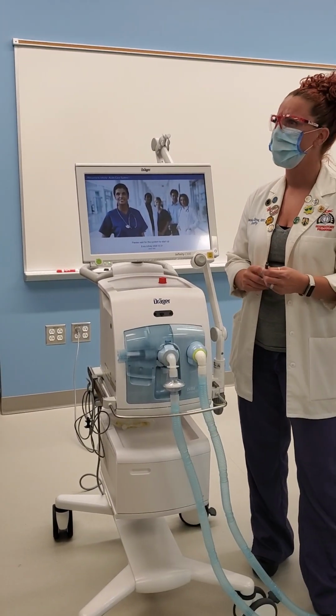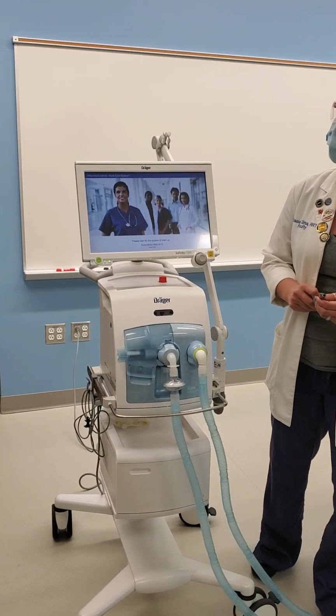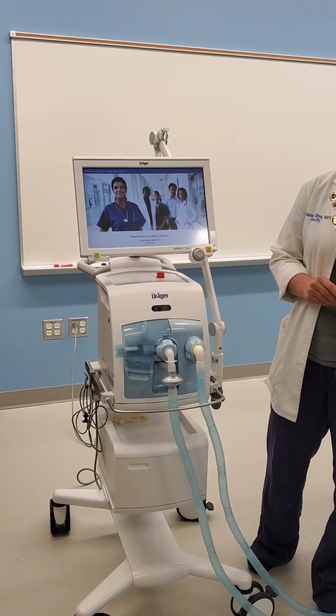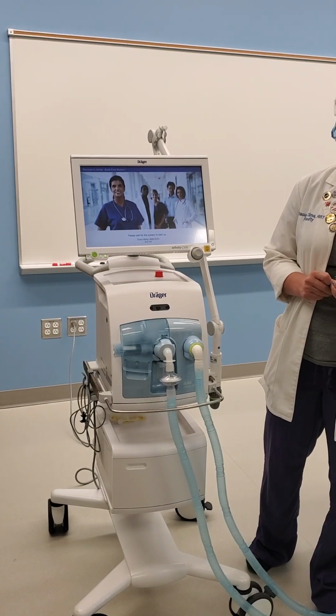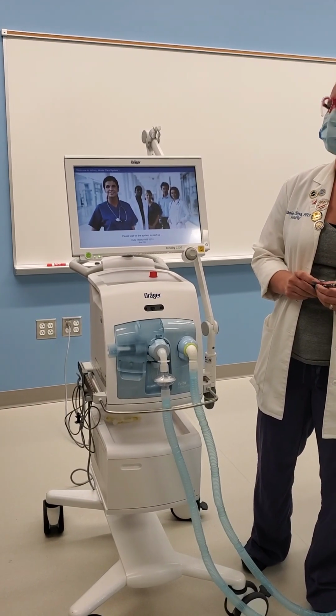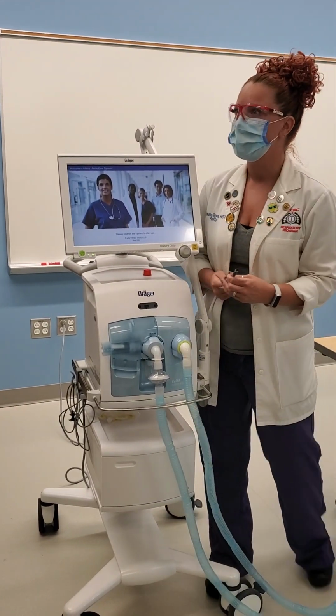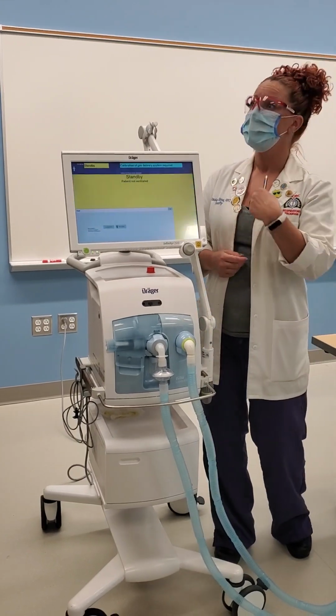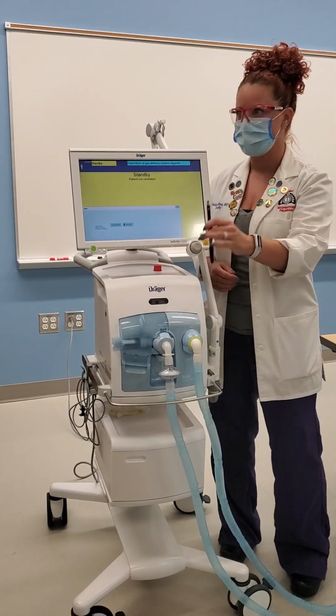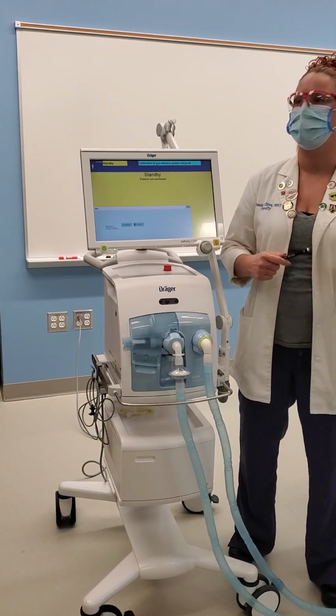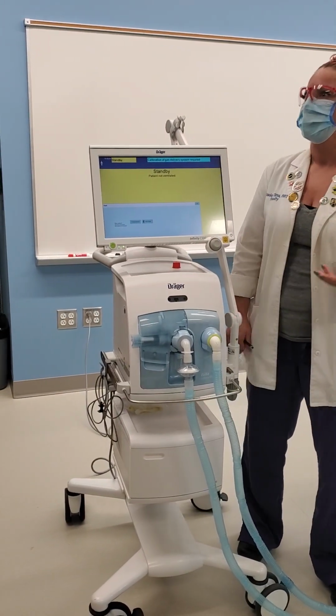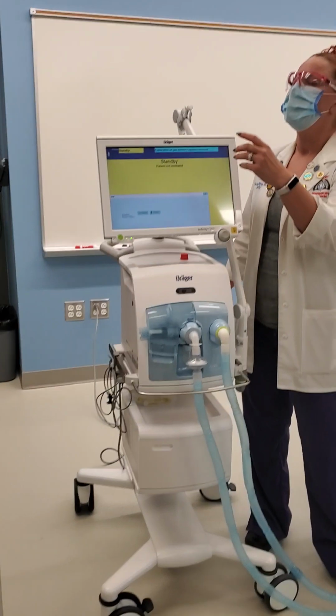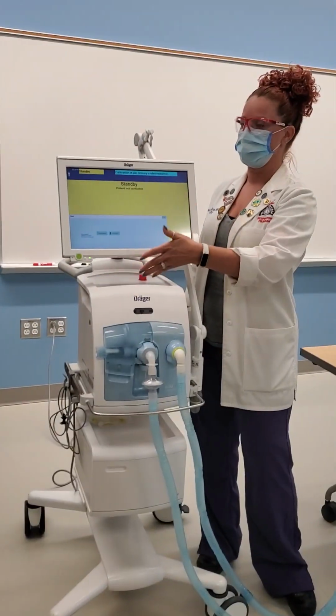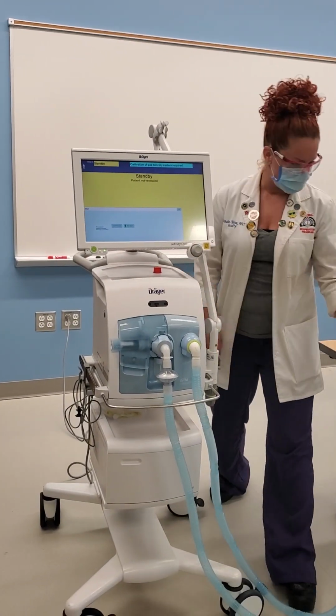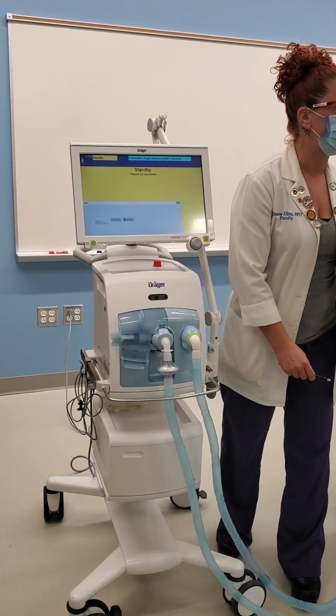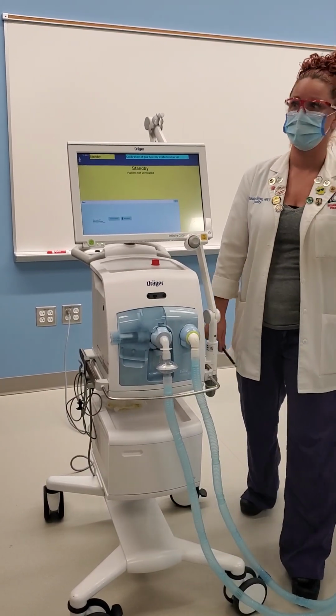Did you have a question? I was just saying, the SSTs on here, I don't like them because you always fail them, because you have to pass the neonatal flow sensor? Yeah, but that's all documented. So if you're not ventilating an adult, it is all logged that you're not ventilating an adult. So technically that would not be a sentinel event. Because you can't test a neonatal flow sensor, because you'll see it plugs in at the Y. And you'll learn more about that when you get to your specialties.